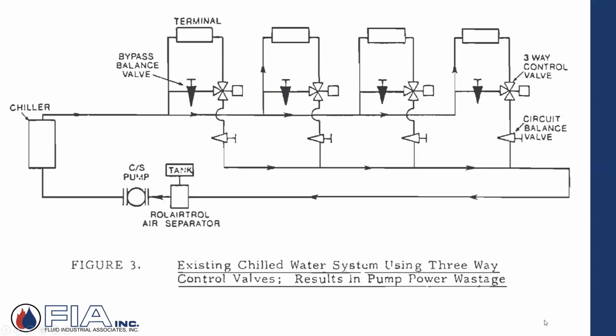It'll go to bypass. Well, that piping right here by itself is not the same resistance as the coil, the terminal unit. So the pipe fitter, but it starts with the engineering community, would establish that when the flow goes through either coil or bypass, the pump doesn't want to see a change. Because if I have a lower pressure drop, the curve is shifting way out to the right. Now I'm going to over pump, more energy being wasted. So I want to balance the bypass piping to simulate the same pressure drop as if it was going through the terminal, so there's no change. So that's what they would do.